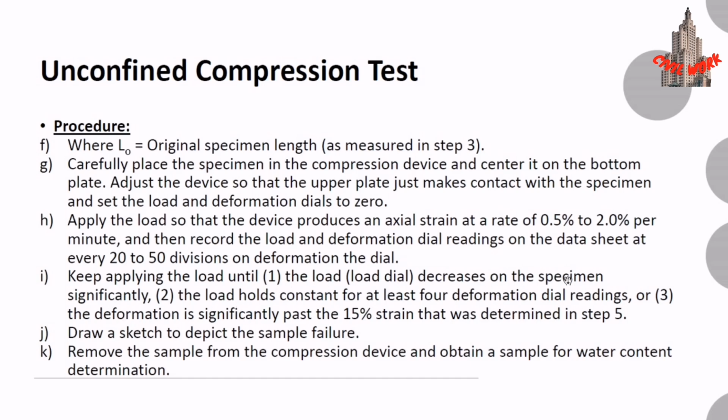These are the three conditions which denote how much time we have to keep applying the load. These are the three conditions. First condition is that the load decreases on the specimen significantly, that the dial reading will decrease significantly.